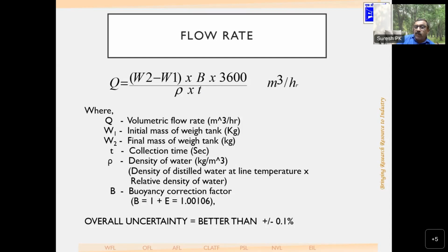But when you are using water or another fluid to fill the tank, the amount of air displaced is different, so the buoyancy effect will be different. So we make a correction. There is an equation by which you can find the buoyancy correction factor depending on the density of the fluid, and that is applied here for finding the mass. And you have density, you have time. So the mass, time and density will give you the flow rate. Mass by density will give you the volume if you want the volume.